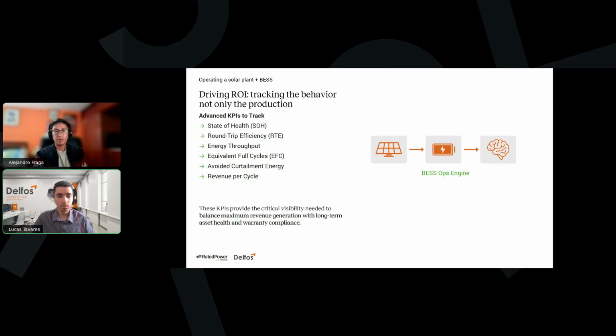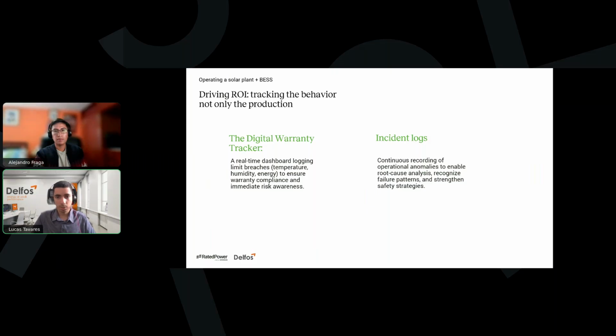For this, we highlight two very important tools. The first is the digital warranty tracker, a living document or dashboard that logs every time the system exceeds important limits, such as temperature, humidity, or energy limits. It matters because you can keep track of this data monthly, and you need to be aware of potential risks and abnormal behavior as soon as it appears. There's also incident logs: automated recording of thermal, voltage, or other operational anomalies to enable pattern recognition and correlation analysis. This allows early identification of recurring malfunctions, supports root cause analysis, and strengthens predictive maintenance and safety strategies.